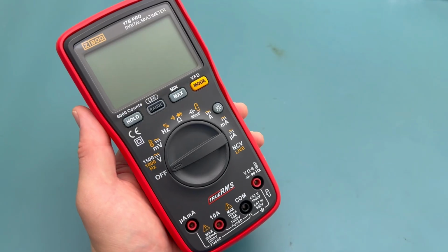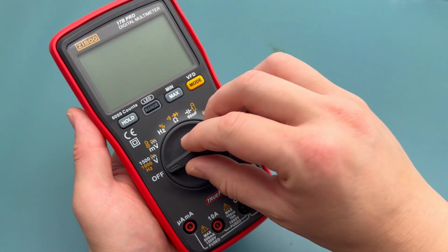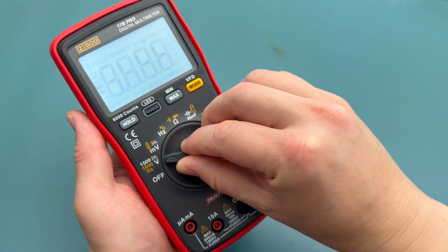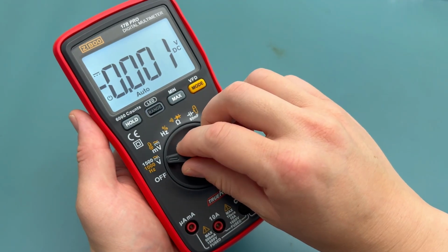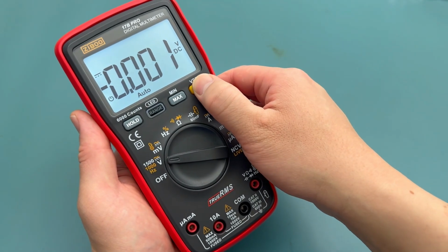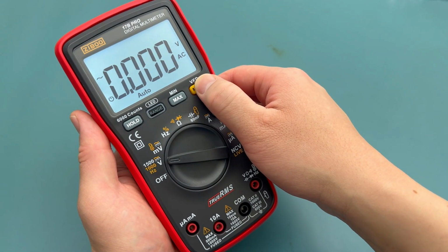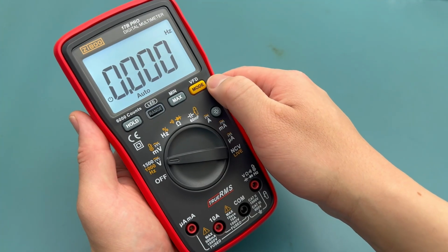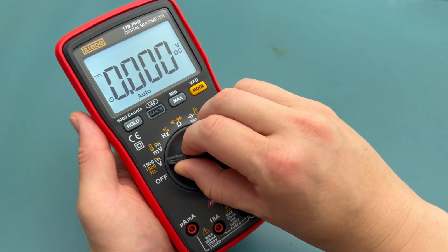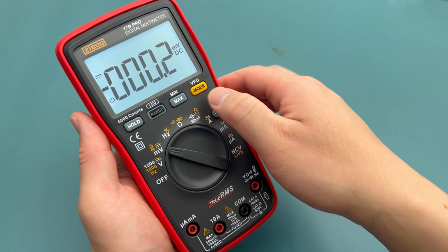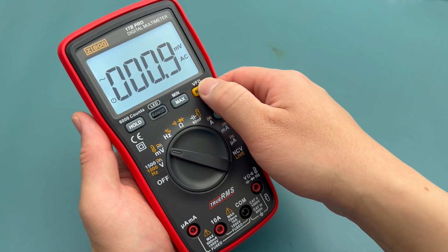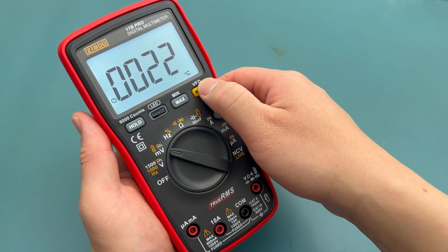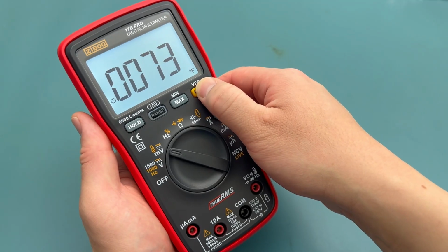Turn the dial to select the desired multimeter function. The first option is to test DC voltage. Press the mode button to switch to AC voltage. Press the mode button again to switch to hertz. Turn the dial to DC voltage in millivolts. Press mode to switch to AC voltage in millivolts. Press mode to switch to temperature setting. Press mode to switch to Fahrenheit setting.